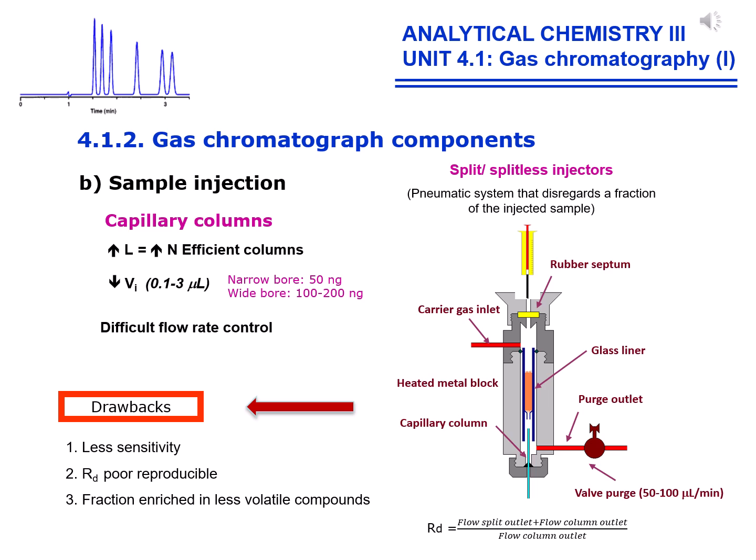As this small flow rate is difficult to control, the on-column injection is not the best option. Therefore, injectors of a different type must be devised. The split/splitless injector, meaning with or without flow division, is the mostly chosen one. This injector consists of a vaporization chamber containing a glass tube inside the injection port called glass liner, into which the sample is injected through the septum.